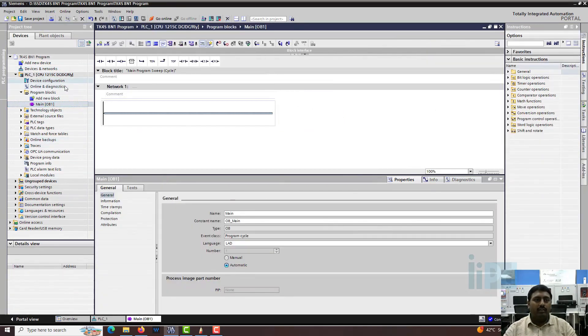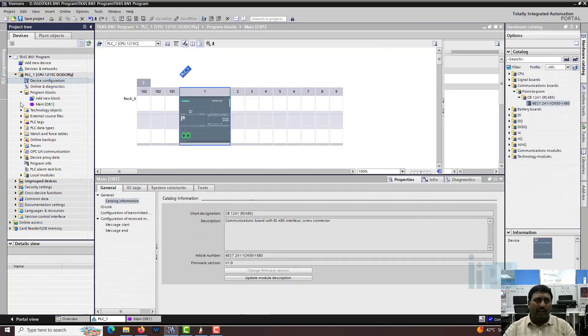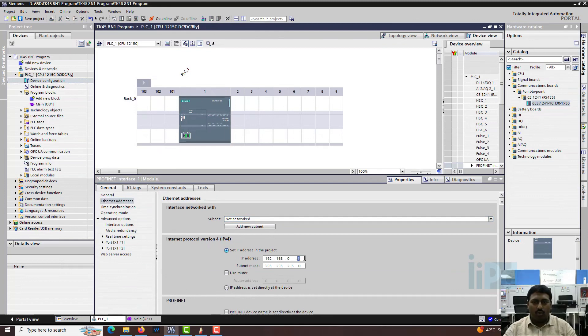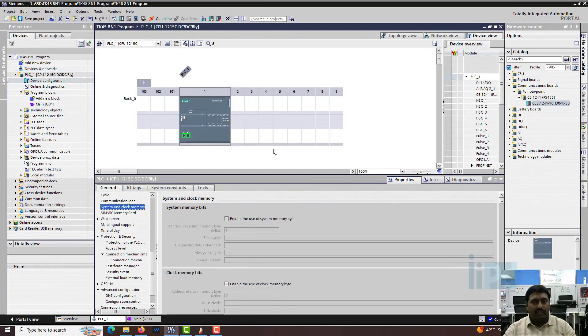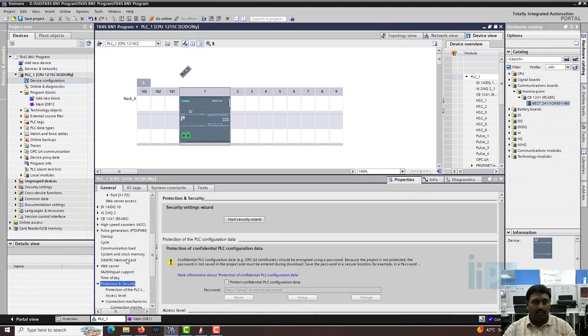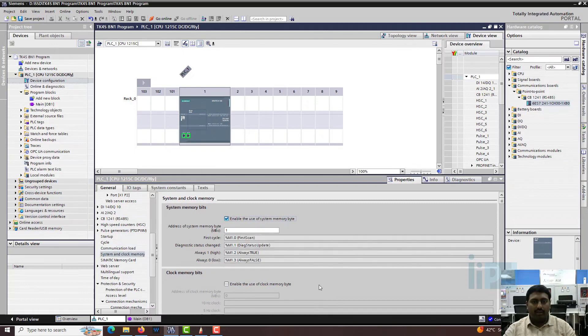We need to do one more thing - let's set up the IP address of the PLC. In our lab, the IP address for this PLC is 0.11. I am just changing it to that. Then on the PLC configuration, I will add and enable the system and clock memory - enable the use of system memory byte and enable the use of clock memory byte.